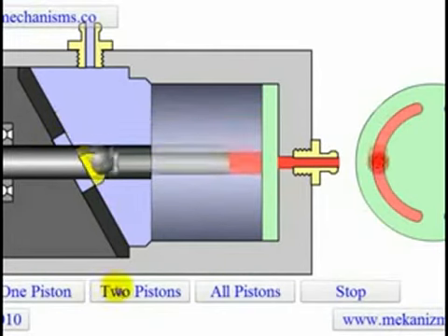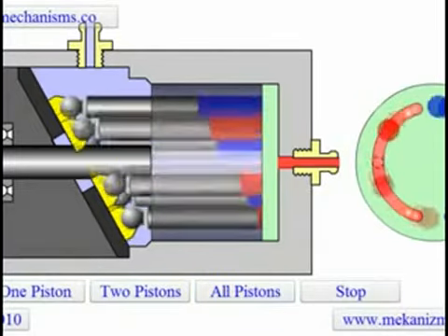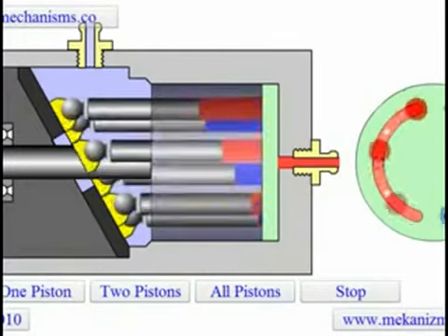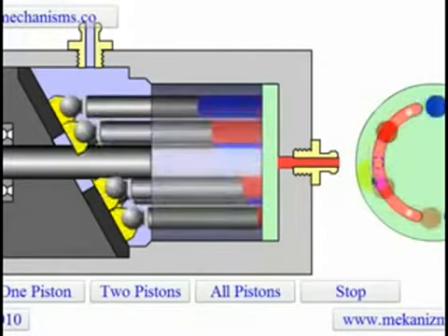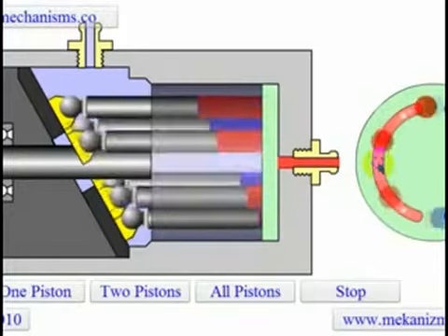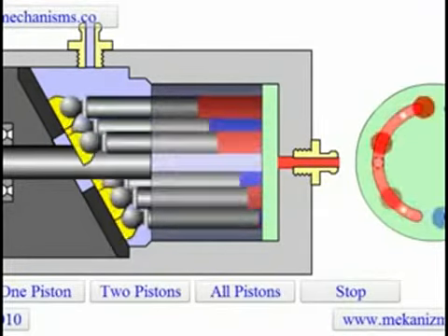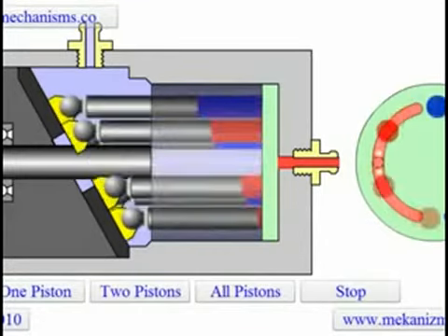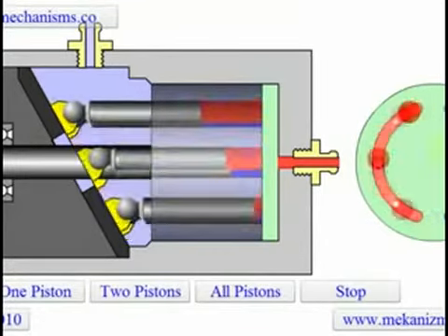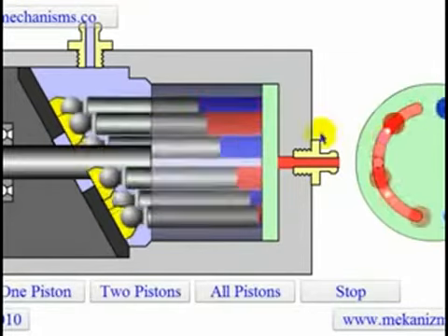The movement of the oil in the crescents is shown with the white bubbles. For high-pressured oil, the bubbles move toward the exit port, indicating that the oil is coming from the cylinders. For low-pressured oil, the bubbles move away from the inlet port, indicating that the oil is coming from the outside. The oil in the blue crescent is sucked in by the pistons moving away from the port plate.